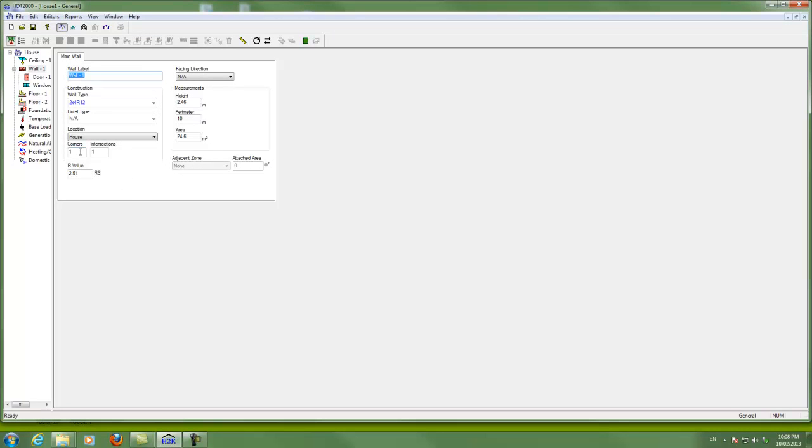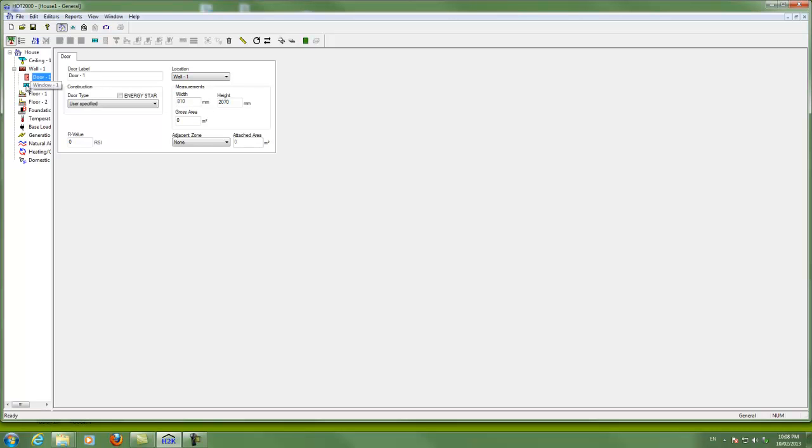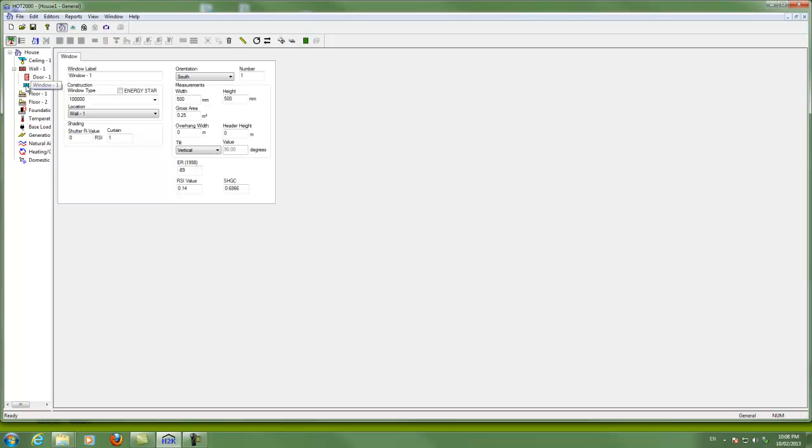Corners and intersections are unique to walls. The idea here is that you typically have more heat loss at the corners and the intersections. And so we put in the number of corners that this wall is going to have. Intersections are intersections with other walls. Corners means inside or outside corners of that wall. These then are the doors and windows that are cut into this particular wall type.